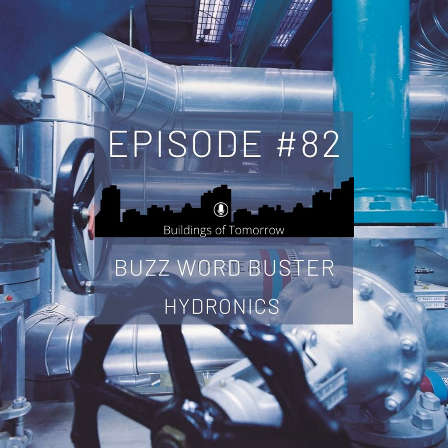So that means we try to figure out how much pressure we need out there at any given time, and this is what we control to. And experience shows this is usually much lower than what we would achieve with delta P proportional. So it gives us an additional saving possibility, but of course we somehow have to measure the resistance out there and the pressure that we provide at the consumer, which means we have to have ways to connect that to the building automation system and then drive it from there.